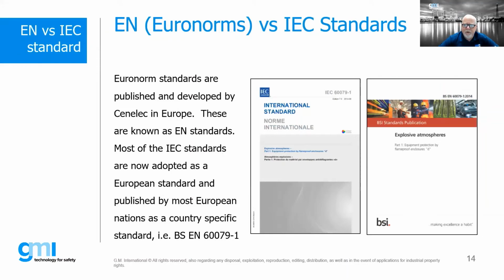Now there's always a question with regards to EN standards or IEC standards. The important thing to know is the difference: if you notice the numbers on the right-hand side of the two standards, there's an IEC version and, in this case, a BSEN standard. The IEC standard is the base standard, developed by Technical Committee TC31. There are members of TC31 who also sit on the committees of Cenelec, who is responsible for writing Euronorm, or EN, standards. Once it gets published by the IEC, Cenelec agrees to take that standard and republish it as an EN standard, and then it gets adopted by each country within, say, the European Union. So it becomes a BS, in the case of a UK standard, a BSEN 60079 standard.